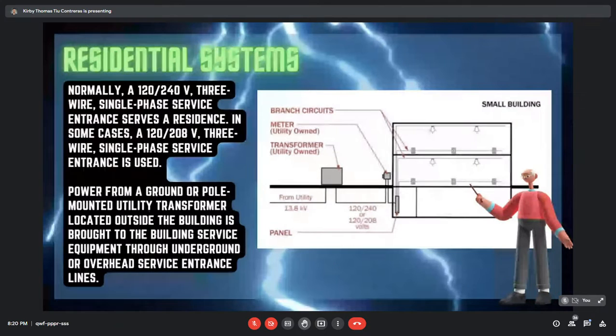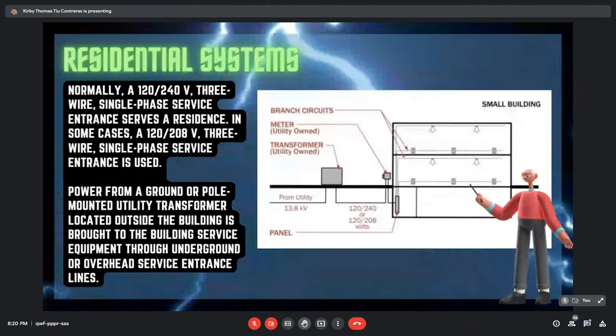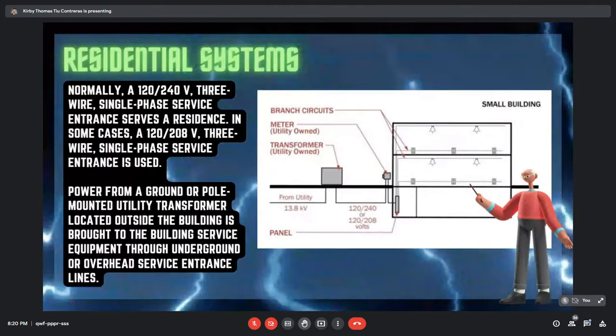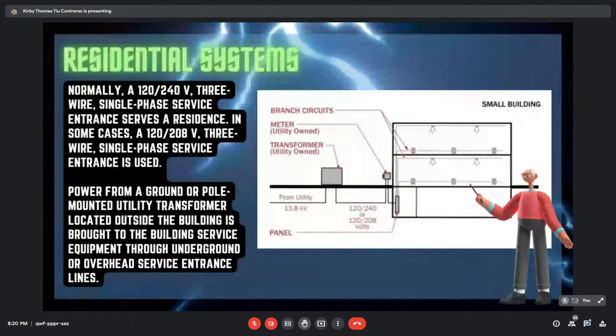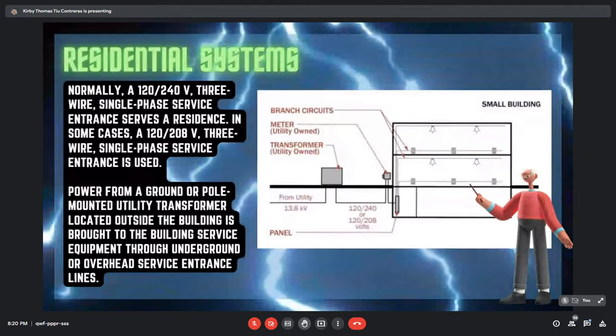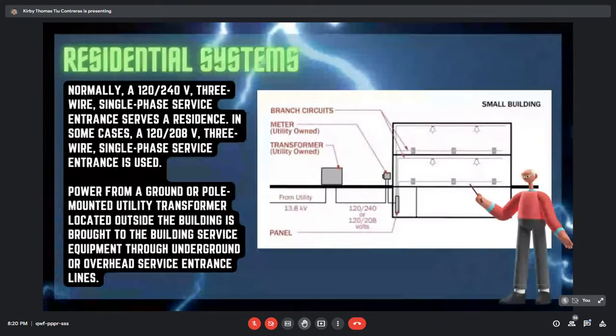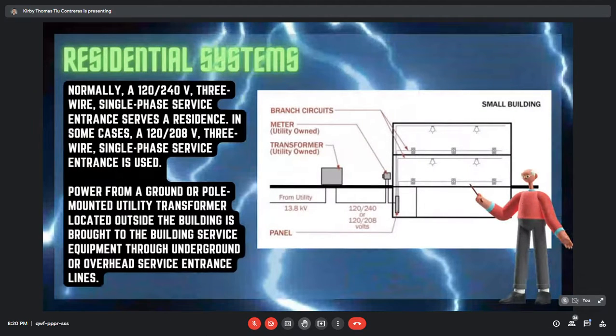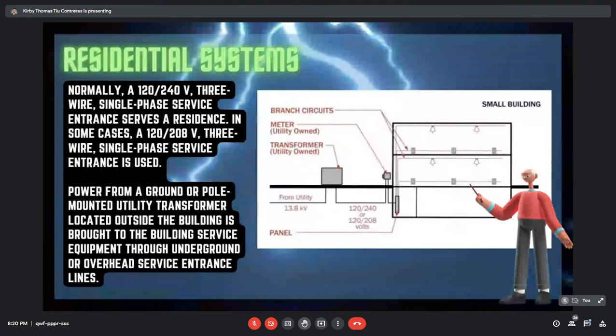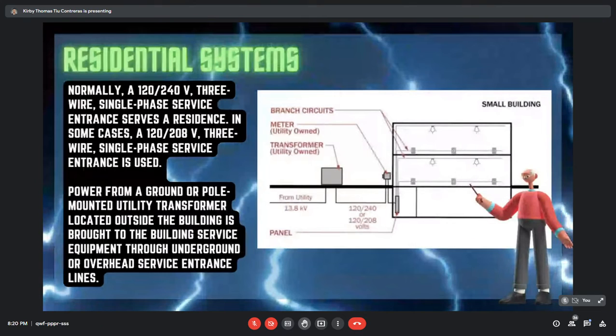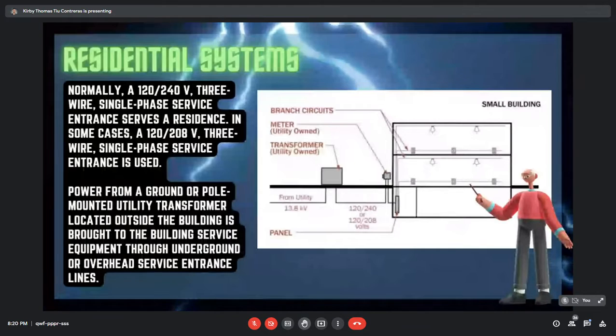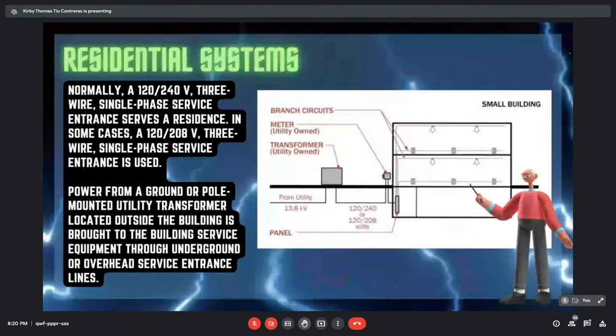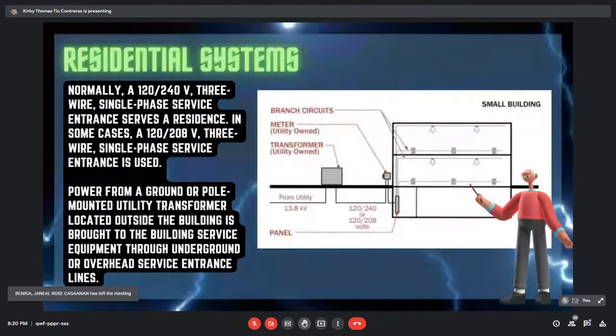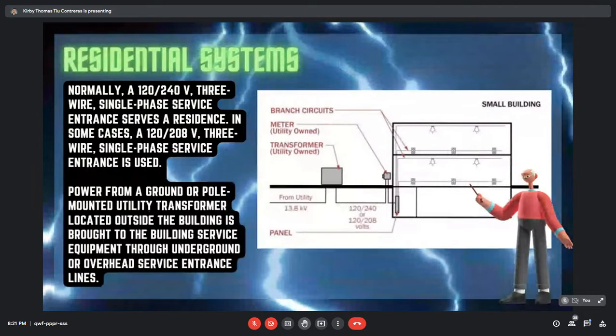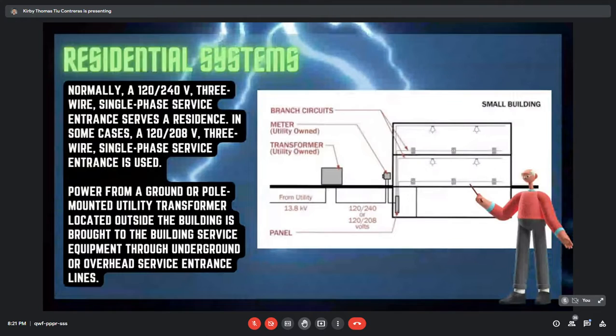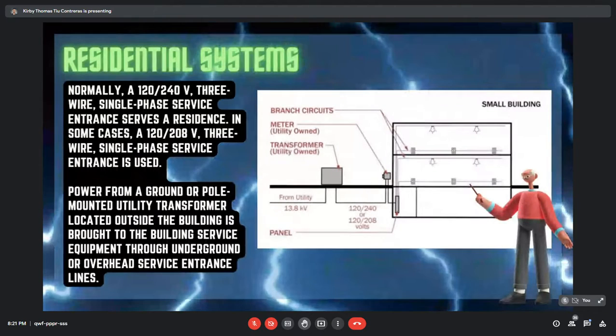The first is that the utility will own the transformer, and the transformer reduces the voltage from 13.8 kilovolt down to 120 over 240 or 120 over 208 volts and then passes the electricity to a meter. After the meter, the power is transmitted into the building, at which point all wiring, panels, and devices are the property of the building owner. Wires transfer the electricity from the meter to a panel board which is located in the basement. So we can see in the picture that the panel is located here in the basement. And then the panel board will have a main service breaker and a series of circuit breakers which control the flow of power to various circuits in the buildings. Each branch circuit will serve a device or a number of devices like convenience outlets.